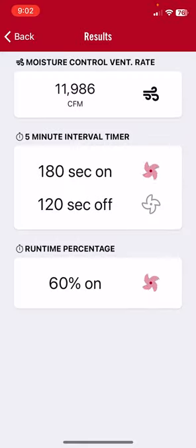So to get rid of that same 1,200 gallons of water, our ventilation rate now has to be about 12,000 CFM, and our fans need to be on about 3 minutes — 180 seconds out of 300.